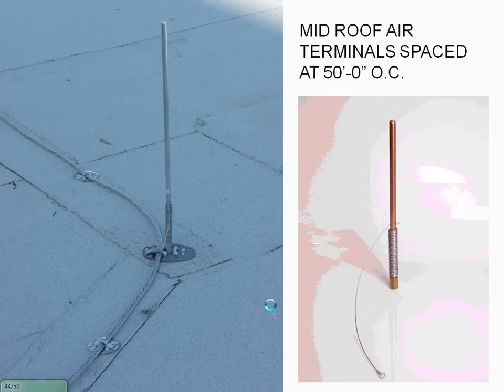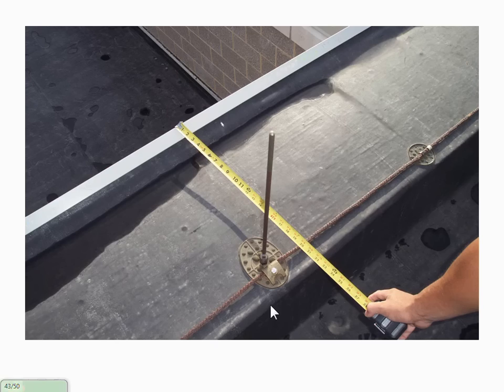Is the air terminal glued? Yeah, it can either be glued to a roof, which in this instance you can see the glue seeping up to the holes here. That's why our bases are made with holes in them. We use an epoxy, set it down, and it sets within a couple days. Or you can use a screw base like this and screw it into the copings. If you're mounting to a metal roof, you never want to screw into it, so we end up gluing instead.